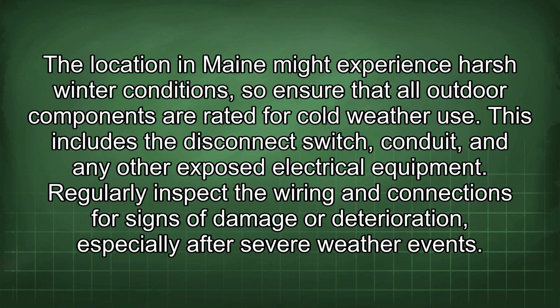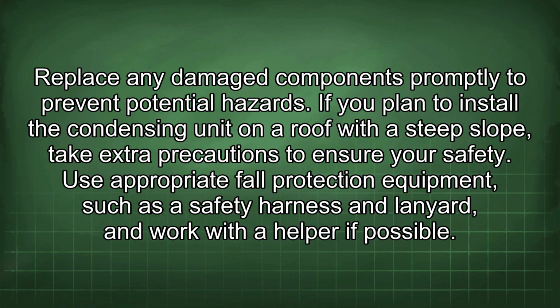The location in Maine might experience harsh winter conditions, so ensure that all outdoor components are rated for cold weather use. This includes the disconnect switch, conduit, and any other exposed electrical equipment. Regularly inspect the wiring and connections for signs of damage or deterioration, especially after severe weather events. Replace any damaged components promptly to prevent potential hazards.